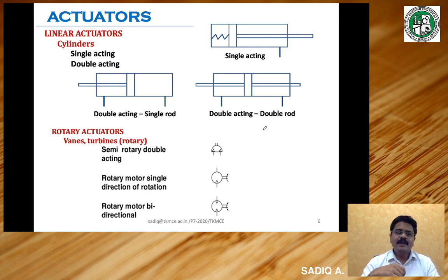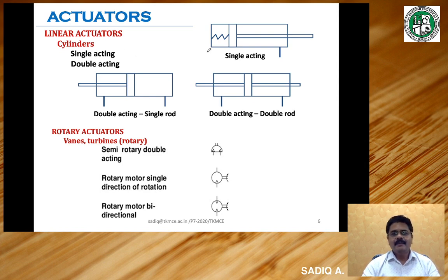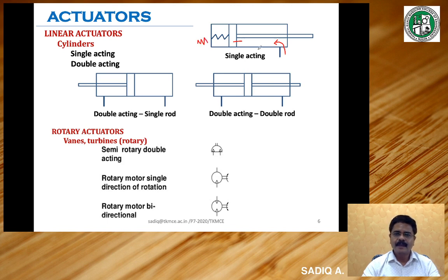Single acting and double acting are a classification for linear actuators. A single acting cylinder has power supply through one side of the cylinder only. There is a spring on the other side, so the reverse movement of the piston happens because of the spring. When control pressure is applied from one side, the piston moves against the spring load. When the pressure is released, the spring action brings it back to the original position. This is a single acting cylinder — power supply through one side only.